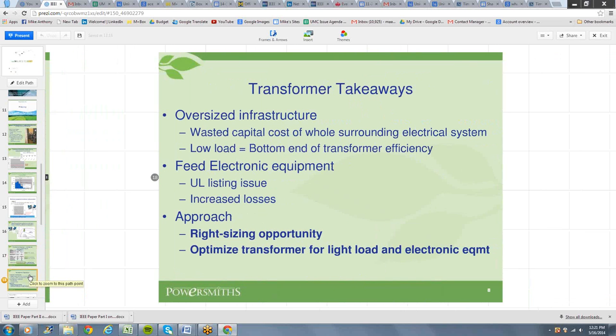So the next slide summarizes the takeaway for transformers. First of all, they're lightly loaded, as a function of code considerations for an electrical system designer allowing for load growth. Overlaid on top of that is the fact that the equipment we're connecting is getting more and more efficient and therefore drawing less and less load, so we really are in a situation where we've got infrastructure that's very commonly 4 or 5 times too big. That's a lot of wasted dollars, right? And from an operating perspective, you're operating right at the bottom range of the transformer. The second reality, we're feeding electronic equipment, so we've got to get a transformer that's UL listed for that application. We've got to recognize that there are increased losses for that profile that have to be minimized if you're going to run an efficient system.